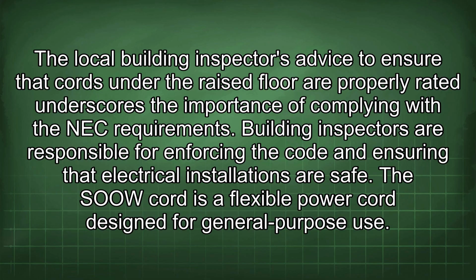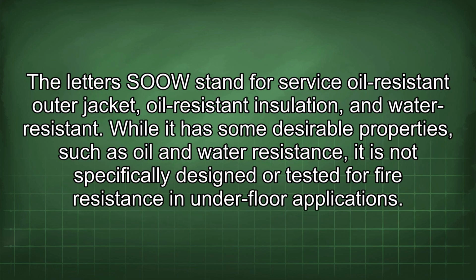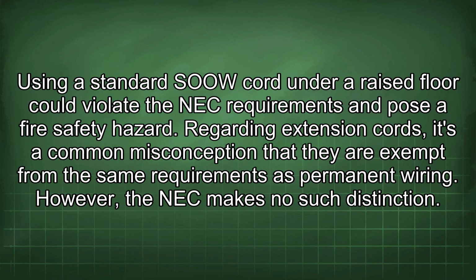The SOOW cord is a flexible power cord designed for general purpose use. The letters SOOW stand for service, Oil Resistant Outer Jacket, Oil Resistant Insulation, and Water Resistant. While it has some desirable properties, such as oil and water resistance, it is not specifically designed or tested for fire resistance in underfloor applications. Using a standard SOOW cord under a raised floor could violate the NEC requirements and pose a fire safety hazard.